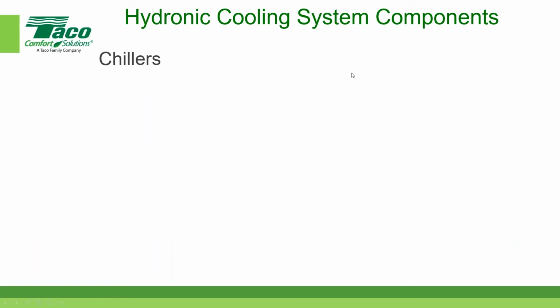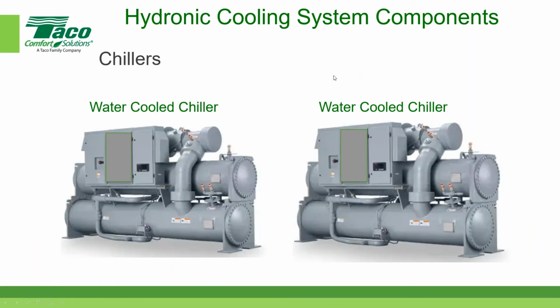And then we have chillers. So today we're going to talk about water-cooled chillers. I'm not going to go into the details of refrigeration. That's another topic that takes a couple of hours all on its own. But the responsibility of a chiller is to provide chilled water to your system. From our diagram previously, in our case, we're going to be supplying chilled water at 42 degrees Fahrenheit, and the return water temperature is going to be 54 for a 12 degree delta T. And as the name implies, water cooled simply means that we are using water to cool the chiller, or to reject heat to the condenser water. And that condenser water is ultimately pumped out into the cooling towers to reject heat to the atmosphere.